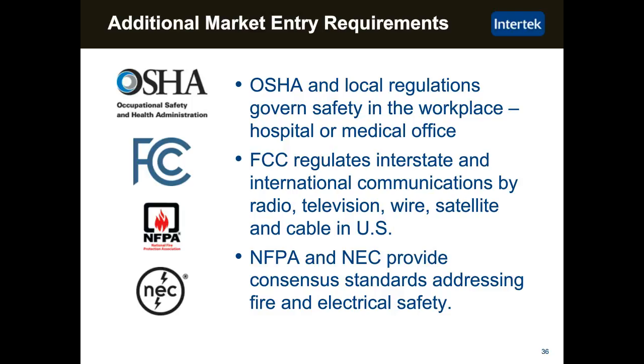So as I mentioned at the start, we talked about the FDA. However, there are other market entry requirements that you have to consider when you're looking at the product. There's OSHA and local regulations that govern the safety in a workplace, whether it's a hospital or medical office, and so there may be requirements associated with your product that OSHA has that may not be linked to patient safety that would be governed by the FDA. For your products that have radio communications, so if it's got Wi-Fi or other things, the FCC regulates those, and you have to be concerned with compliance there. And then, of course, you have fire codes and electrical safety codes for permanent installations and other types of things. So be aware that there are other regulations that may be required above and beyond the FDA.